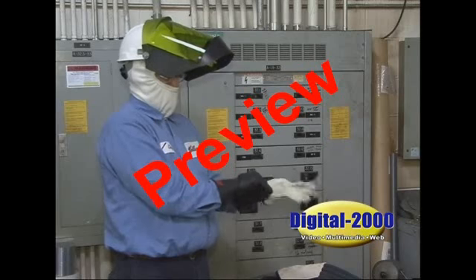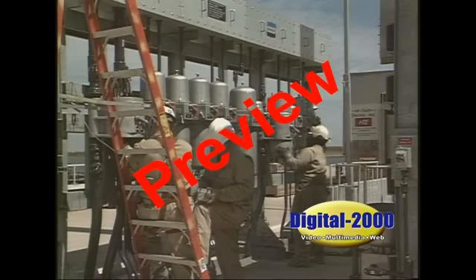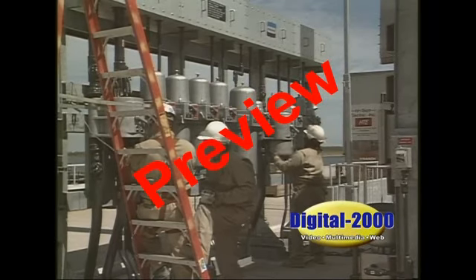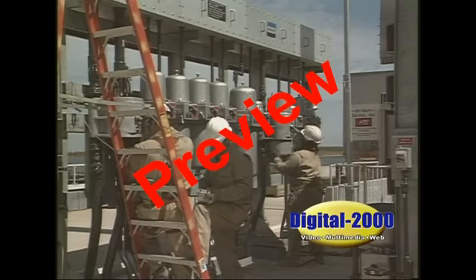NFPA 70E has specific requirements for PPE depending upon the potential hazard. Protective equipment sufficient for protection from an electrical flash would be required for any part of the body which could be within 3 feet of the fault. That is why the assessment is so important in establishing boundaries to select the appropriate PPE that will protect you in the event of a flash.